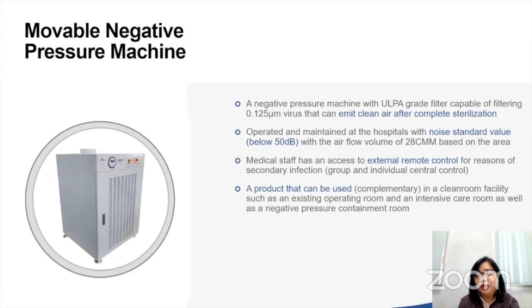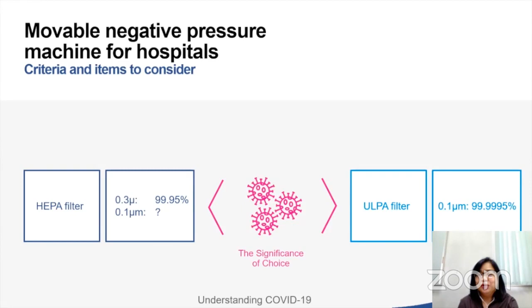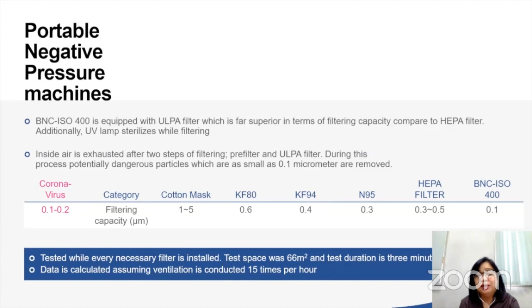The nice thing about this is that because they also have UV lamps, they come with an external remote control, so you don't get scared that you have to turn it on and enter the COVID room. You can actually turn it on remotely. So this can be used in a clean room facility, such as any existing ORs or any existing ICUs. These machines have not just HEPA filters, but ULPA filters, which can filter up to 0.1 micrometer. So it gives you a lot of assurance when it comes to filtration of the air. These portable machines, like the BNC-ISO 400, are equipped not just with ULPA filters, but also with UV lamps, which additionally sterilize the room.